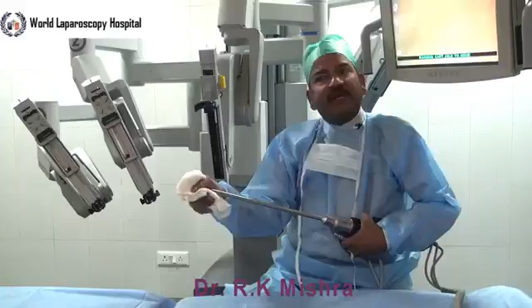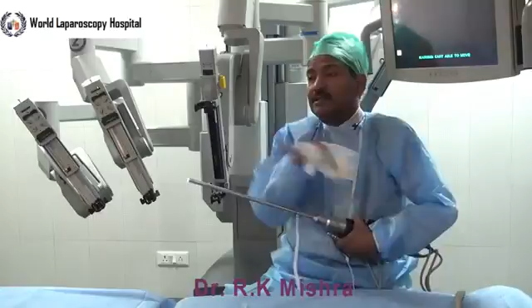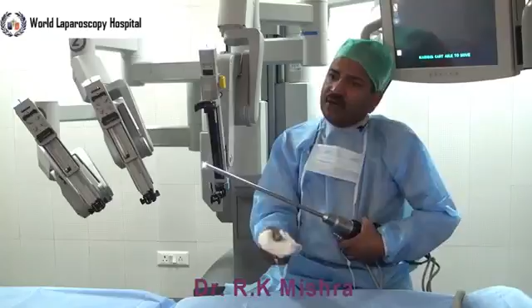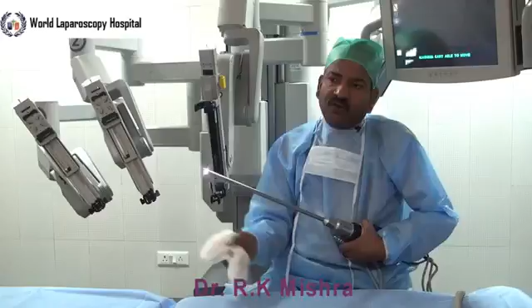You have to do white balancing of only one camera. Automatically the other camera will get white balanced. You don't have to do both individually, because both cameras are synchronized with each other by the software. So if you are changing the shutter of one camera, the other will automatically change. If you are setting any setting of one camera, the other will change. You do not have to focus separately also. One focus itself will do.